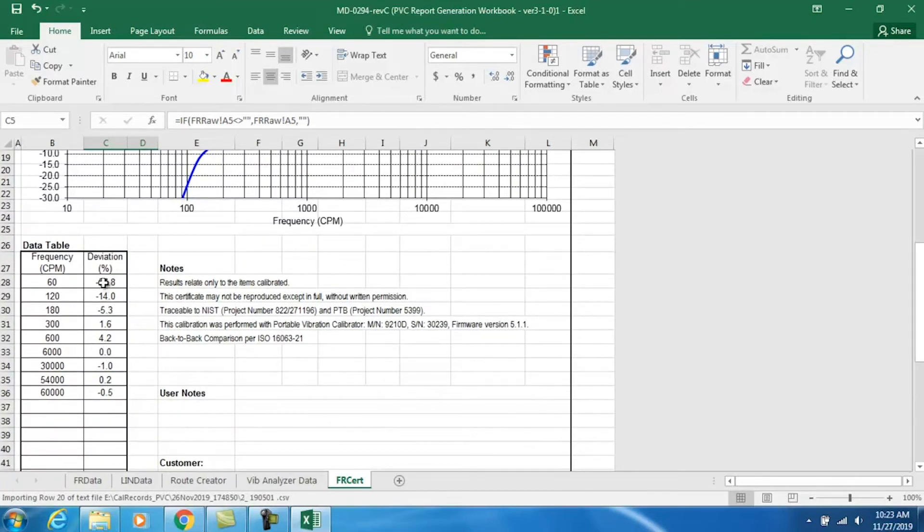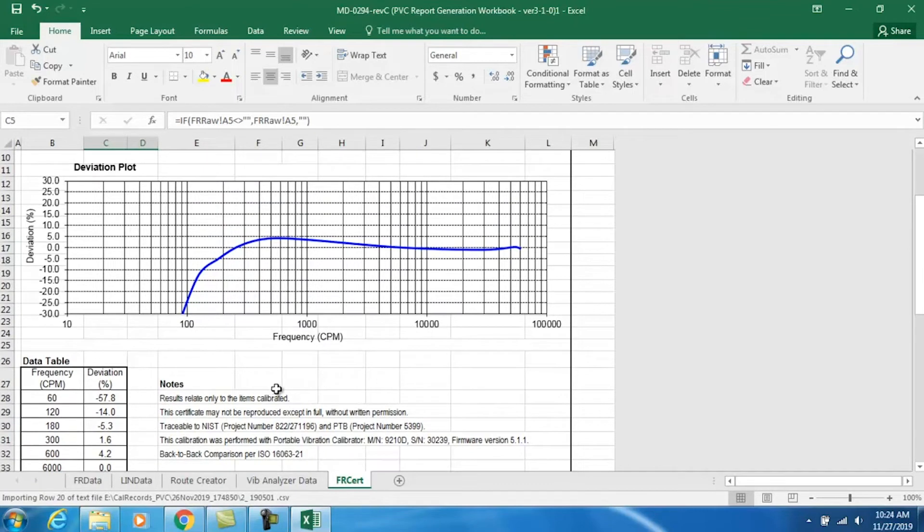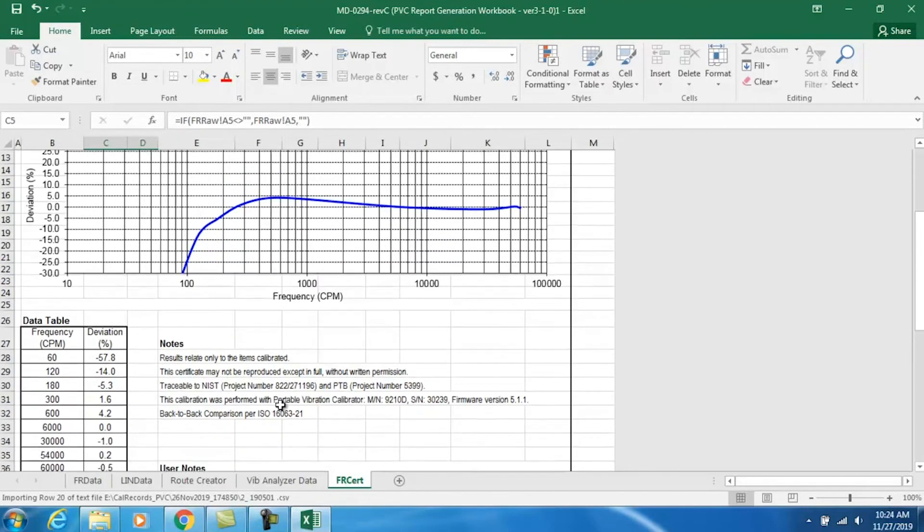You can see that we were within specification at every data point. Remember that the specification at 120 cycles per minute is plus or minus 3 dB, so that allows us to be 29% down when you convert that to percentage — so only being 14% down is certainly well within specification. Also remember that the sensor is only specified to 90 cycles per minute. I tested it at 60 cycles per minute just to illustrate the fact that it does have a very steep roll off, so it's very important to understand the output of this sensor if you're using it at 90 cycles per minute or on a 120 cycle per minute slow speed fan. It's very important to understand the voltage in millivolts per inch per second or millivolts per millimeter per second that the sensor is outputting.